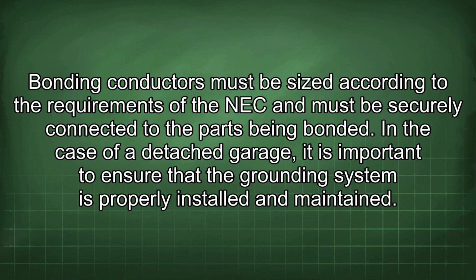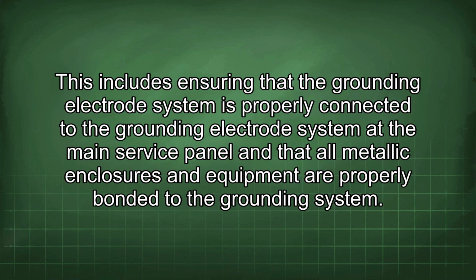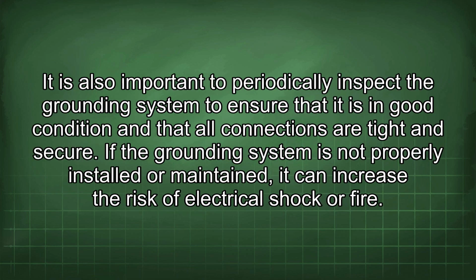Bonding conductors must be sized according to the requirements of the NEC and must be securely connected to the parts being bonded. In the case of a detached garage, it is important to ensure that the grounding system is properly installed and maintained. This includes ensuring that the grounding electrode system is properly connected to the grounding electrode system at the main service panel and that all metallic enclosures and equipment are properly bonded to the grounding system. It is also important to periodically inspect the grounding system to ensure that it is in good condition and that all connections are tight and secure. If the grounding system is not properly installed or maintained, it can increase the risk of electrical shock or fire.